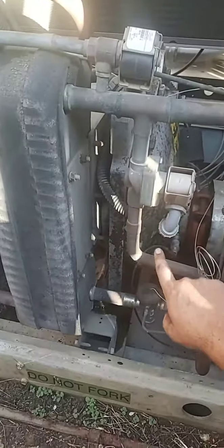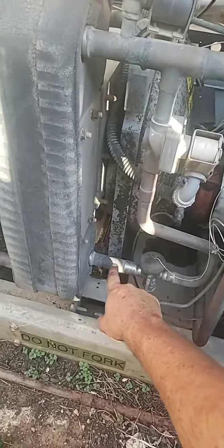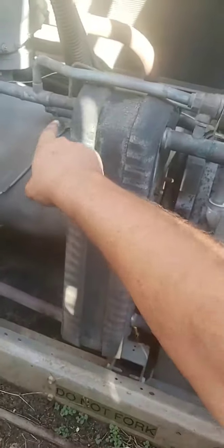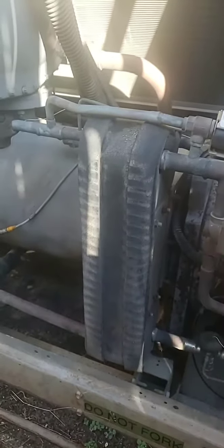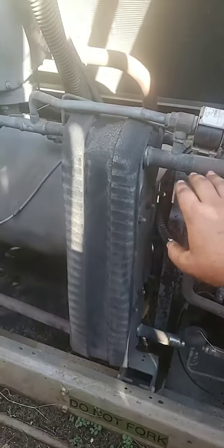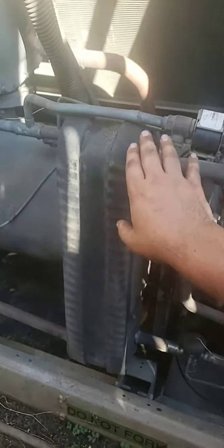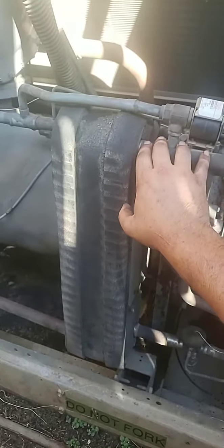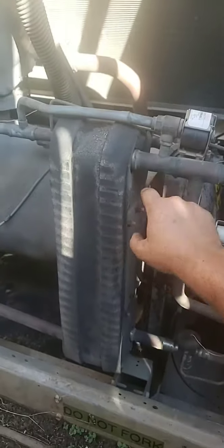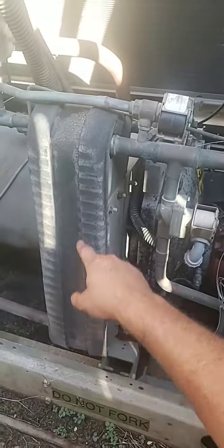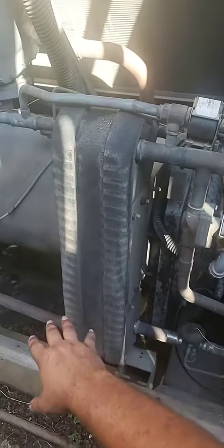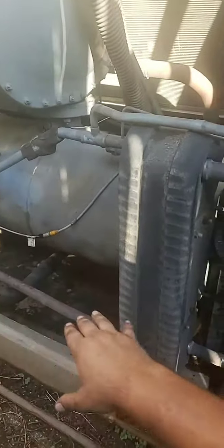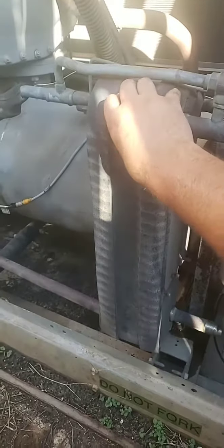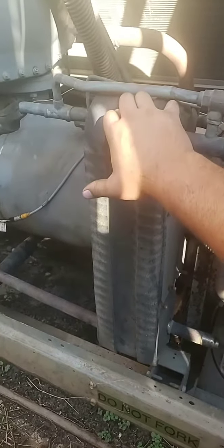But coming off of this line, we're actually running back through this TXV into that inlet port and back out up here on this outlet port. What they're doing here is using a little bit of liquid coming off the condenser, and I'll throw some example numbers out. They're taking, say, this 8 to 10 degree subcooled refrigerant, and by running a cooling circuit through this heat exchanger, they're able to achieve more like 15 to 20 degrees of subcooling coming out to hit our EXV. And so its sole purpose is to get better efficiency, hence the name economizer.